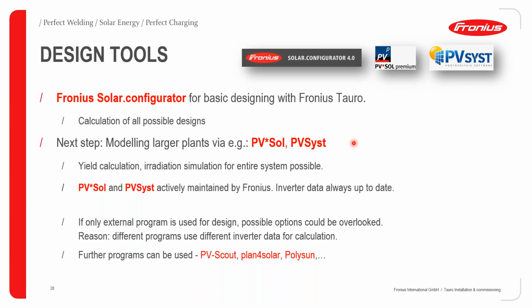However, we would like to caution that you should not rely only on third-party tools. Also make use of the Fronius Solar Configurator, because if you rely only on third-party tools, you might overlook some possible options as far as design considerations on your string lengths are concerned. The reason is that different programs use different inverter data for calculation. So regardless of the system design tool you're using, always make a point of referring to our Fronius Solar Configurator to confirm that you have designed the appropriate cable or string length for the particular inverter, because things like irradiation and temperature are very well factored into the Fronius Solar Configurator.